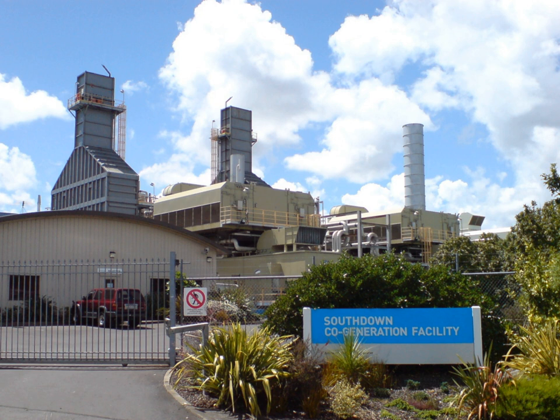Fuel cells generate electricity and heat as a by-product. The advantages for a stationary fuel cell application over Stirling CHP are no moving parts, less maintenance, and quieter operation. The surplus electricity can be delivered back to the grid. PEMFC fuel cells fuelled by natural gas or propane use a steam reformer to convert methane in the gas supply into carbon dioxide and hydrogen; the hydrogen then reacts with oxygen in the fuel cell to produce electricity. A PEMFC fuel cell based micro CHP has an electrical efficiency of 37% LHV and 33% HHV, and a heat recovery efficiency of 52% LHV and 47% HHV, with a service life of 40,000 hours or 4,000 start-stop cycles, equal to 10-year use.